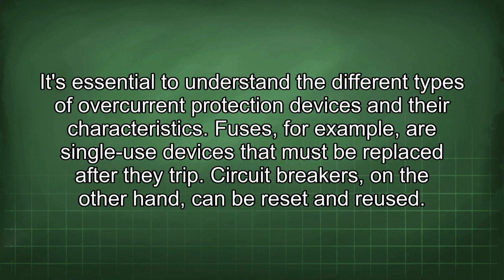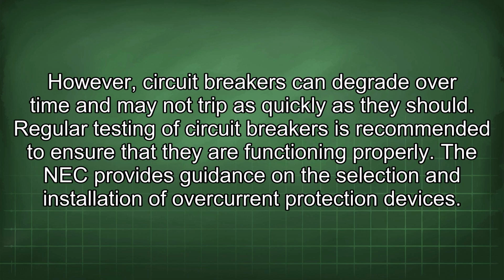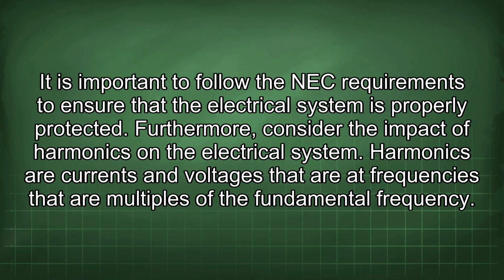It's essential to understand the different types of overcurrent protection devices and their characteristics. Fuses, for example, are single-use devices that must be replaced after they trip. Circuit breakers, on the other hand, can be reset and reused. However, circuit breakers can degrade over time and may not trip as quickly as they should. Regular testing of circuit breakers is recommended to ensure that they are functioning properly. The NEC provides guidance on the selection and installation of overcurrent protection devices. It is important to follow the NEC requirements to ensure that the electrical system is properly protected.